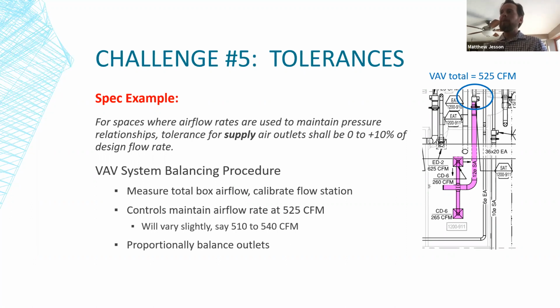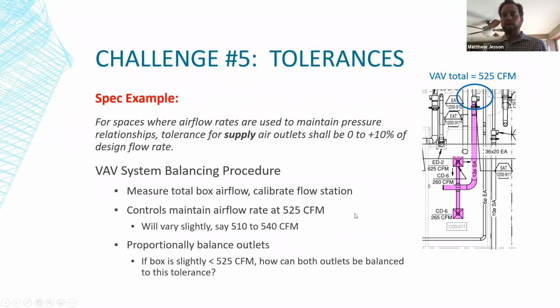That's going to be your total airflow in reality coming out of that box. So our next step is to proportionally balance the outlets. I want 260 on this one, 265 on this one. So I'm going to measure them with the flow hood and adjust one of the dampers to get them proportionally in balance. But if the box is a little below that 525, or realistically even exactly at 525, how can I get both outlets to be at least their design airflow up to 10% above? In this case, the issue really is that the way the system controls and the control tolerance is sort of in conflict with what my specified tolerances are for balancing.